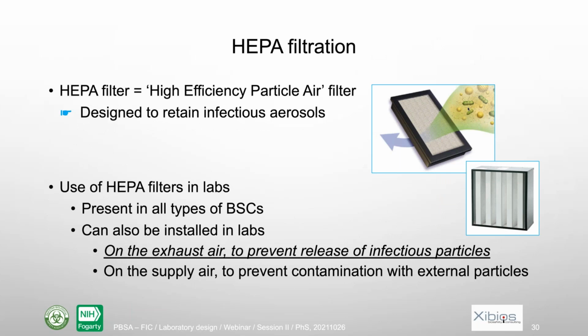Another possible way to manage possible contamination through the air is to use filters, and the filters that are used for biosafety purposes are mainly HEPA filters. So they retain infectious particles in aerosols, and that could be infectious particles, but they will retain any type of aerosols, actually, of particles. Such filters are present in all types of biosafety cabinets, but they could also be installed in labs.